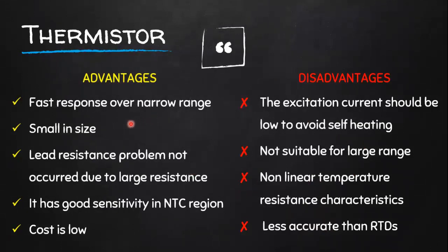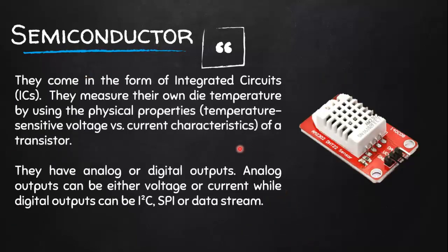We can find the resistance of a thermistor by using an ADC component like a microcontroller. The advantages of thermistors include a very fast response over a narrow range of temperature, small size, and the lead resistance is not a problem because thermistors have a very high resistance value. They have good sensitivity in the NTC region and their cost is low compared to RTDs and thermocouples. The disadvantages include that excitation current should be low to avoid self-heating, they are not suitable for large temperature ranges, their behavior is nonlinear with temperature changes, and they are less accurate compared to RTDs.